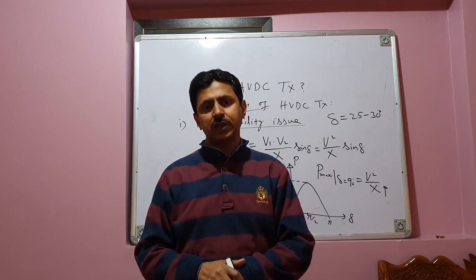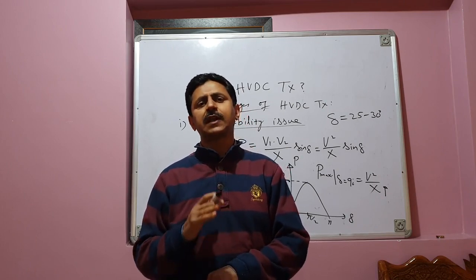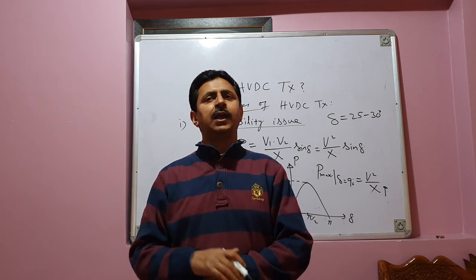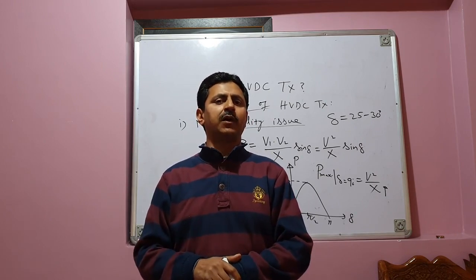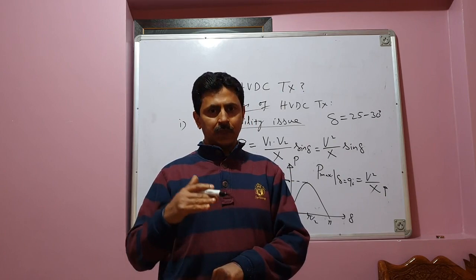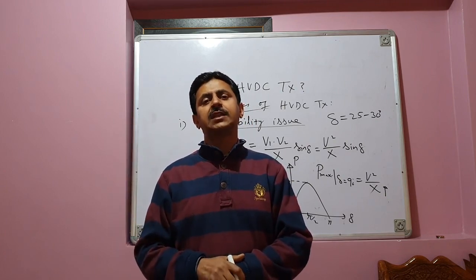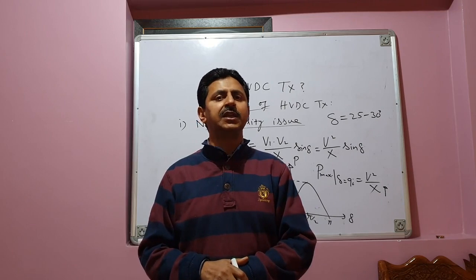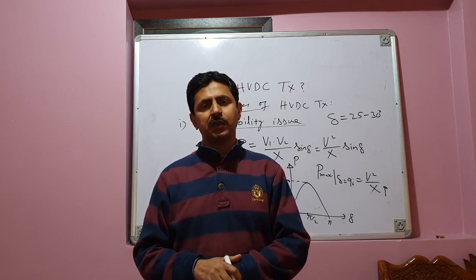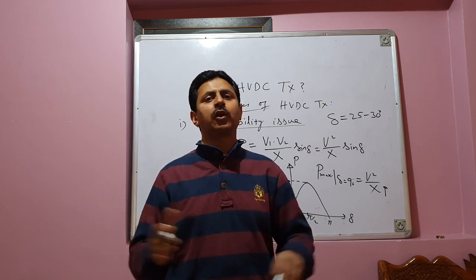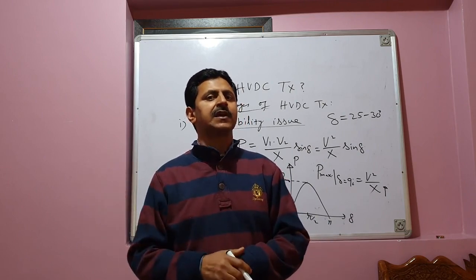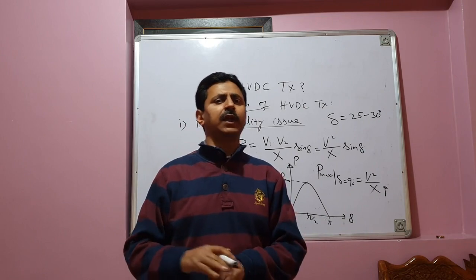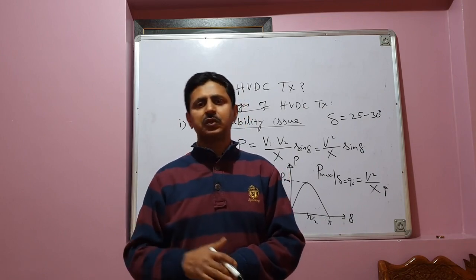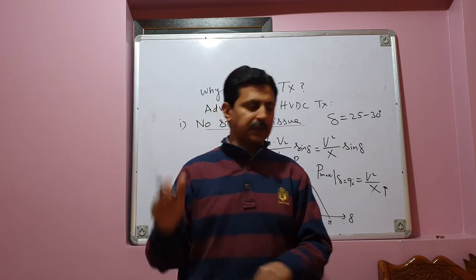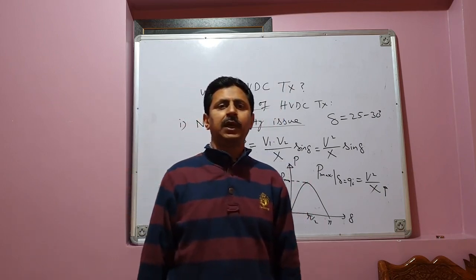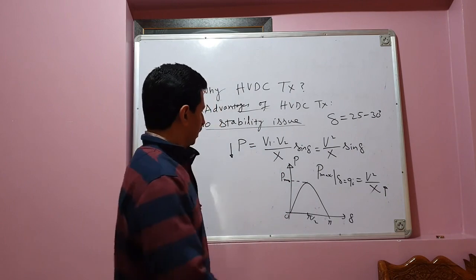So therefore, the first and foremost point, a very important advantage which an HVDC power transmission system offers over AC power transmission system, is that there is no stability issue in HVDC power transmission. We can transmit bulk amounts of power over a DC transmission line over very long distances at very high voltages. Stability is not an issue, distance is not an issue, of course. So this is the first point which goes in favor of HVDC transmission. This is the first advantage.